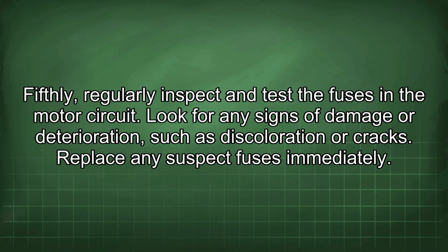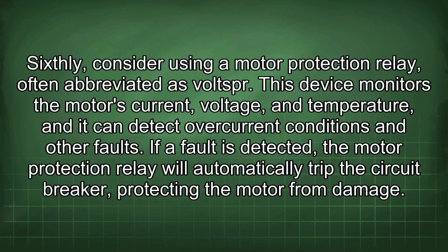Fifthly, regularly inspect and test the fuses in the motor circuit. Look for any signs of damage or deterioration, such as discoloration or cracks. Replace any suspect fuses immediately. Sixthly, consider using a motor protection relay. This device monitors the motor's current, voltage, and temperature, and it can detect overcurrent conditions and other faults. If a fault is detected, the motor protection relay will automatically trip the circuit breaker, protecting the motor from damage.